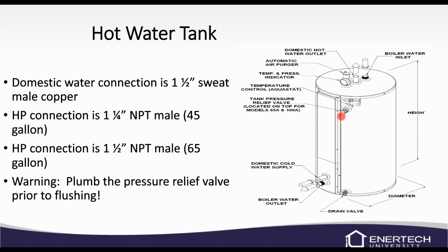There is a pressure relief. It will open at 30 PSI. Go ahead and plumb that to a drain before you flush. As you flush, you might get pressure higher than 30, or whatever the pressure relief valve is. I believe it's at 30. But you could get above that pressure and then it'll spit some water out. So if you pipe it to a drain, it'll just go down to the drain and not that big of a deal. So just keep that in mind.